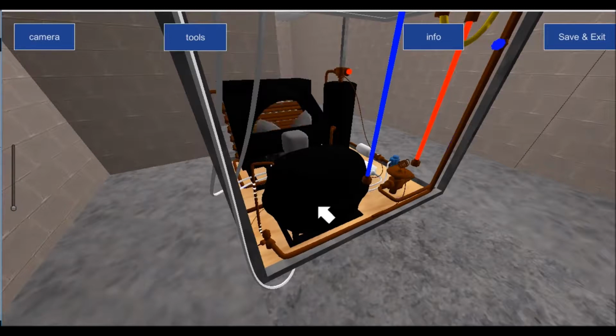Some of these hermetically sealed compressors, if they are rattly, there's not a lot you can do about it. I've seen some people, maybe a bit of trial and error, add a little bit of oil, but there's no way of knowing how much oil is in this type of compressor. I've seen other people give it a smack of a rubber mallet when it starts to get noisy. But usually if it's starting to get noisy, it's an indication that the compressor's on its way out.